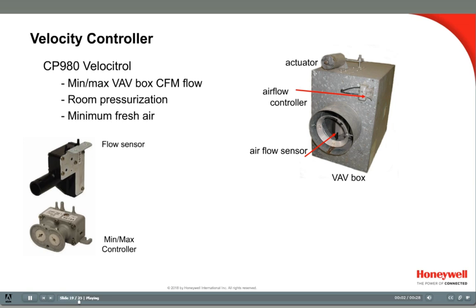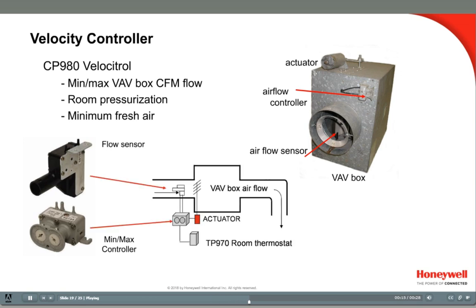Although not classified as a relay, the CP980 Velocitrol is an air velocity sensor with a pneumatic controller used to control air flow in VAV boxes. There are direct-acting and reverse-acting models. Here it is used with a room thermostat to control CFM through a VAV box, providing pressure-independent air control. It is also used in a variety of other air flow control applications.